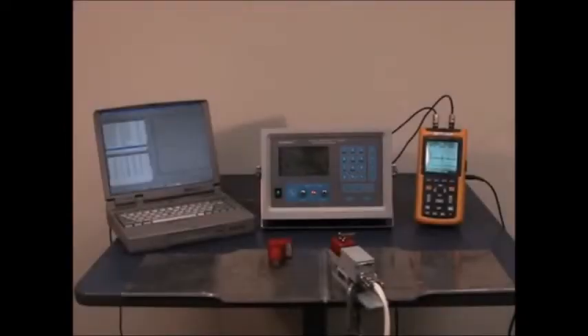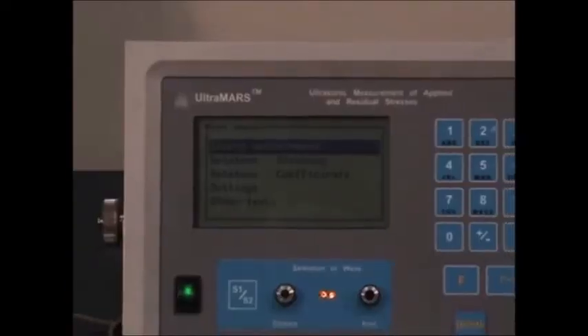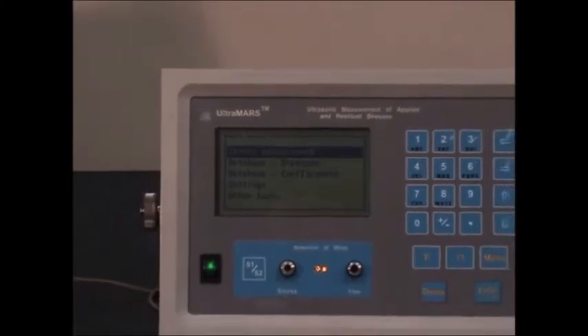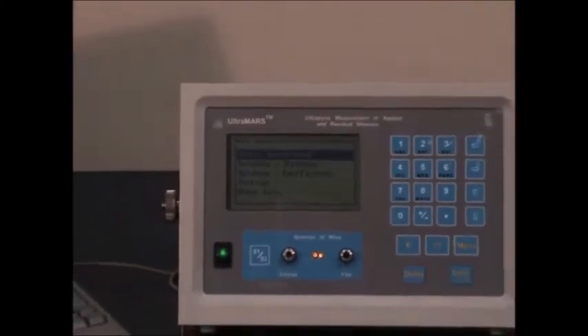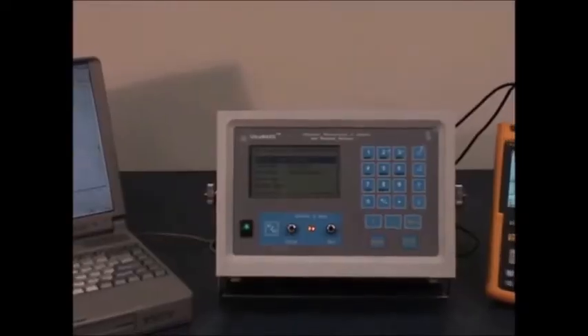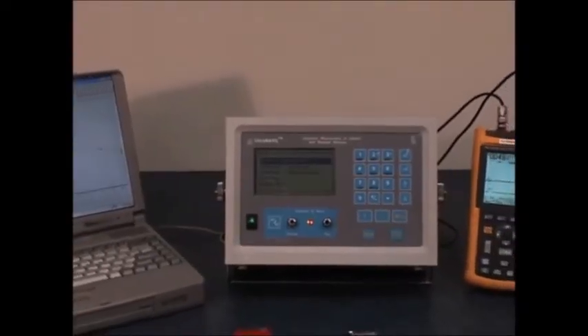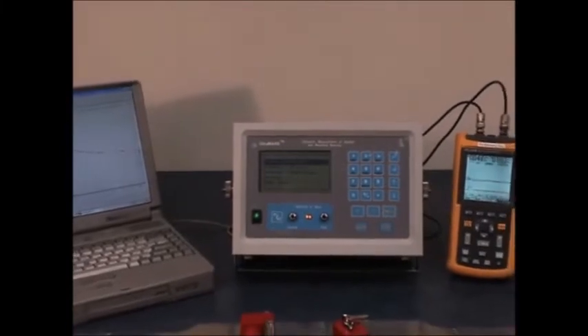The ultrasonic computerized complex was developed for measuring residual stress in laboratory and field conditions. It includes a measurement unit with supporting software, a laptop computer with an advanced database, and an expert system that analyzes the influence of residual stress on the fatigue life of welded elements.